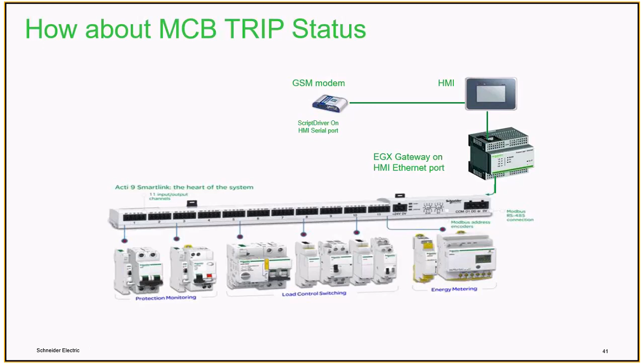How do I do this? This is an Acti9 module where I can plug and play every MCB and different electrical switchgear component into this link module, which has Modbus address mapping. This way, I can connect to a PLC or HMI with address mapping — for example, 40001 for motor or MCB on/off, and 40002 for trip condition. This can be tracked directly with the help of IoT.